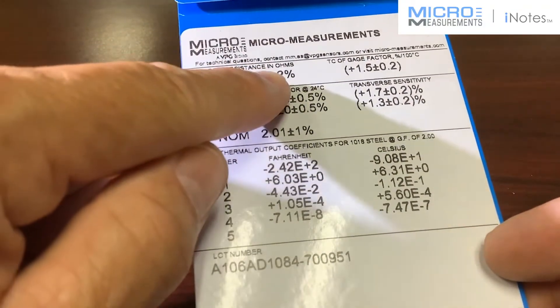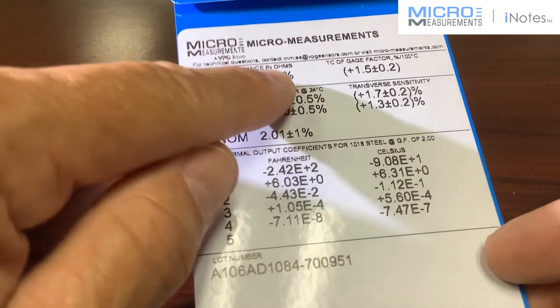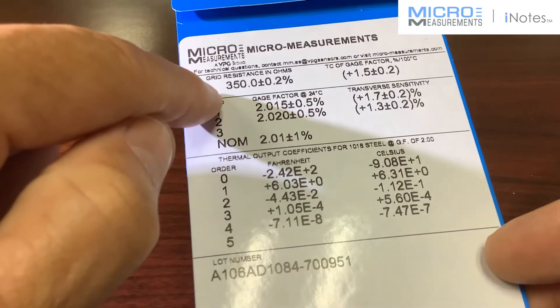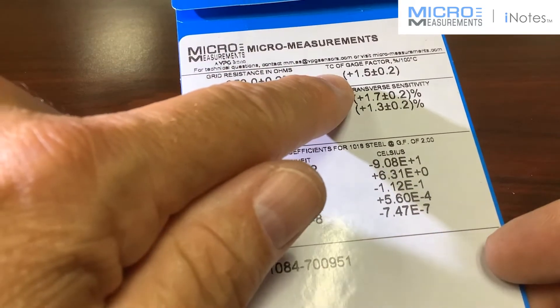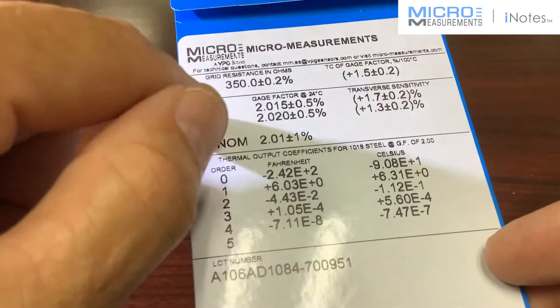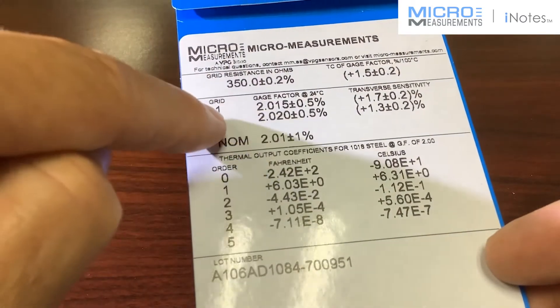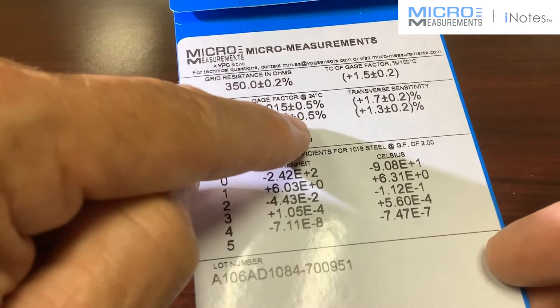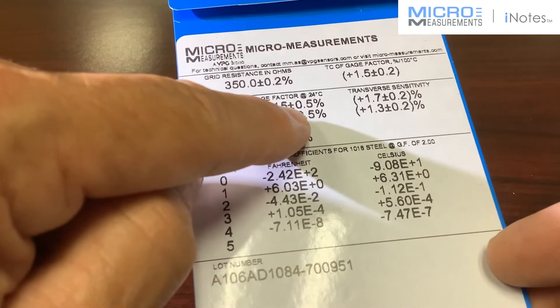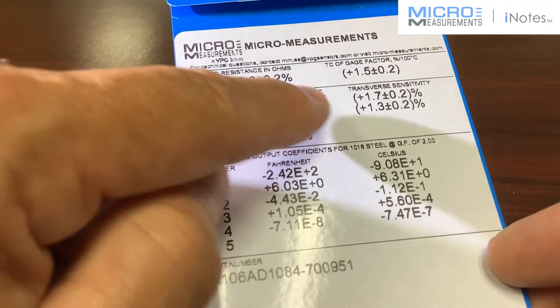We've got the resistance is 350 ohms plus or minus 0.2%, and that's even tighter than what the traditional CEA series gauges would be. You've got the temperature coefficient of gauge factor, 1.5% for 100 degrees C. You've got gauge factors for the two separate grids with a half a percent tolerance, which is typical for what we would have offered with the traditional gauges.